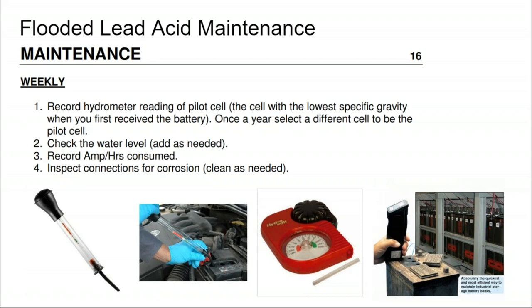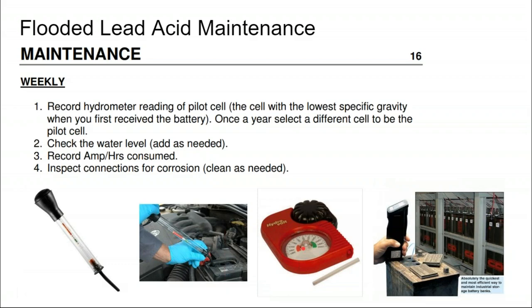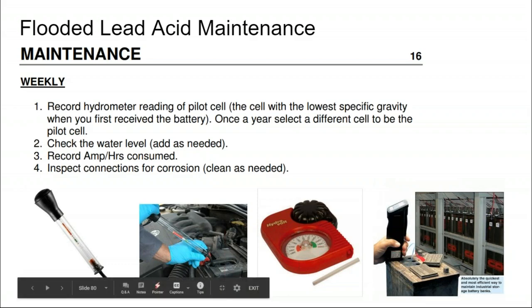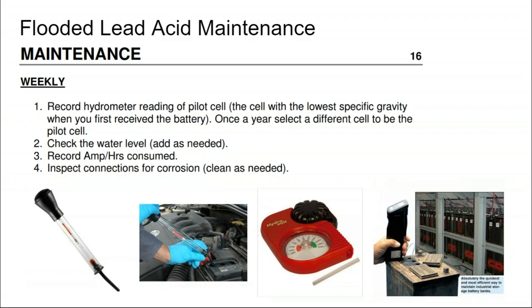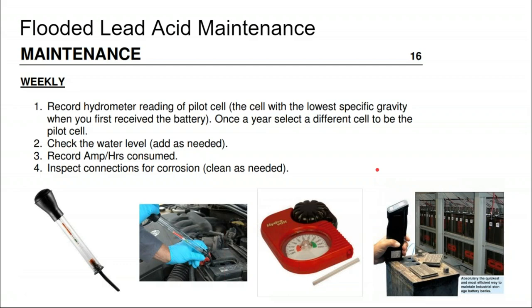This is the main maintenance task of lead acid: opening up that tube, sticking something down in it, and writing down the number. It takes more time because you can't just do it cavalier like you can with pumping water into the battery. So watering is pretty easy, but testing every battery monthly for specific gravity is not so enthusiastically greeted a task.